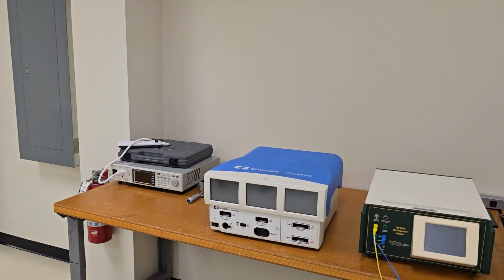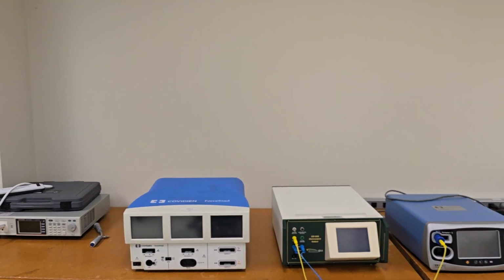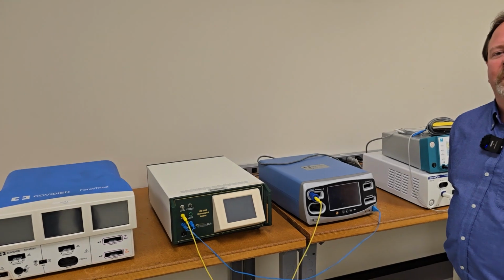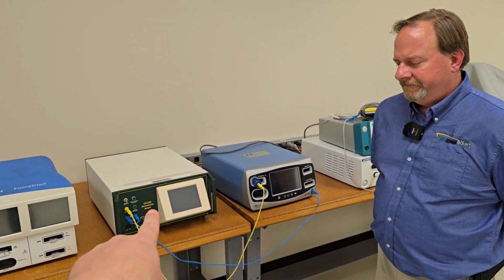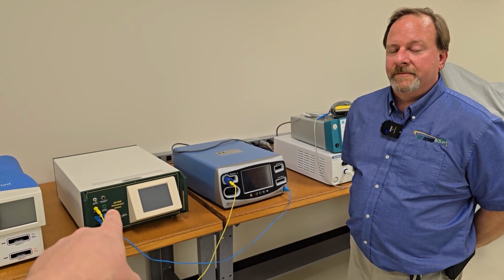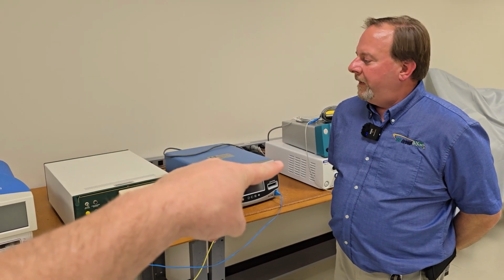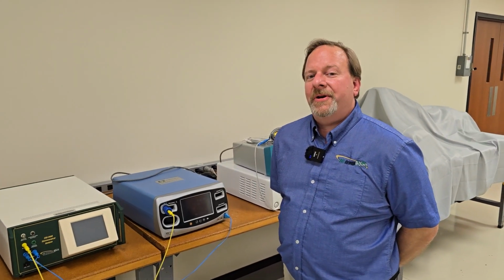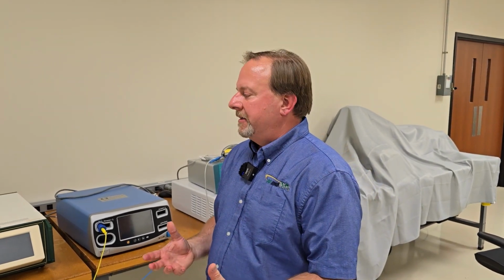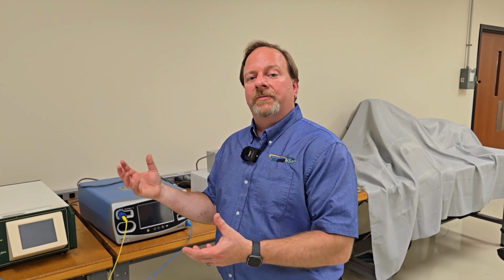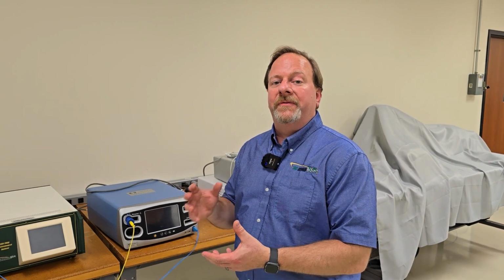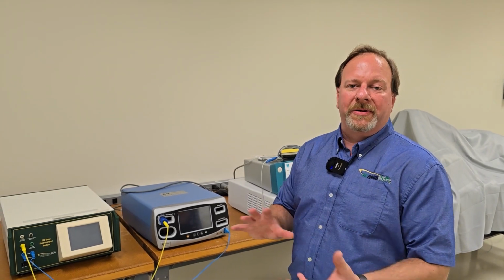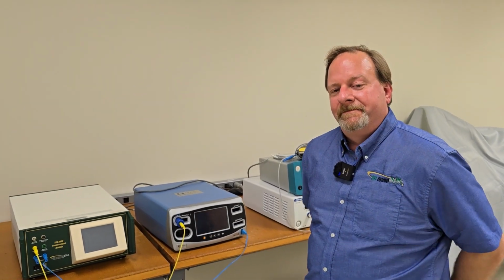Here's a question for you - let's say I have an old ESU analyzer, do you guys offer a trade-in or something on the old ESU analyzers in order to get the high frequency capabilities? You don't have to trade it in, we offer an upgrade package. What that gives you is you can send it in, we'll replace the analog circuitry and give you the advanced 2400H without having to buy a whole new unit. We'll recalibrate it, bring it up to speed, make sure it's all working properly, and send it back.